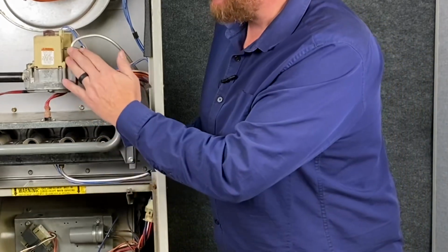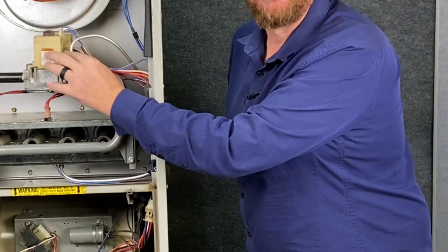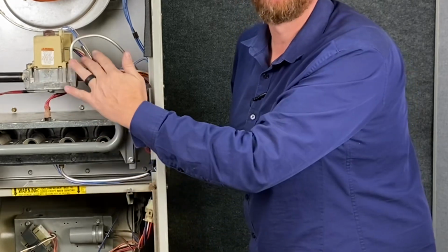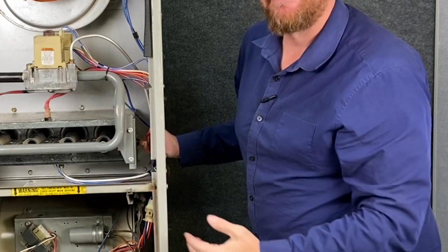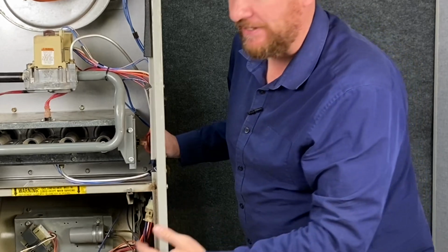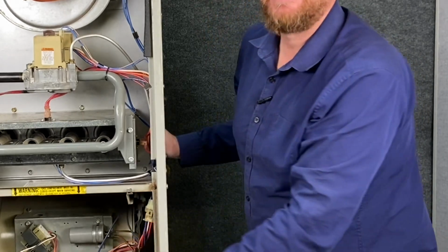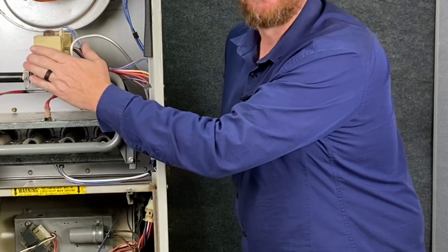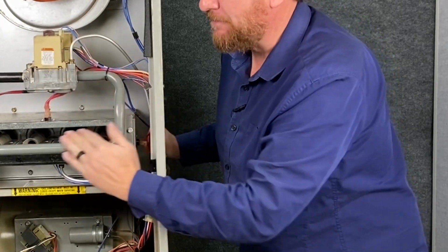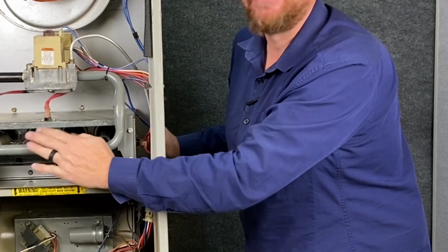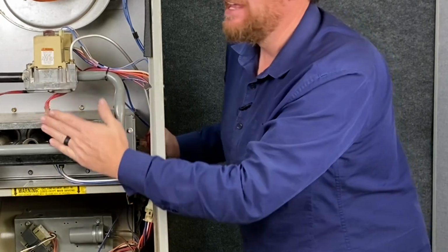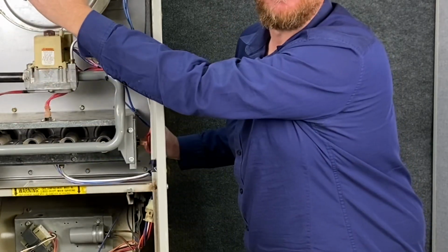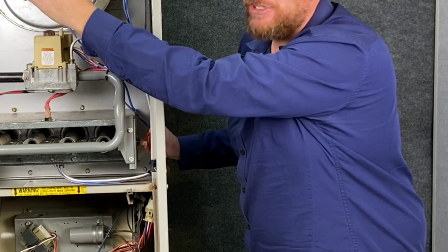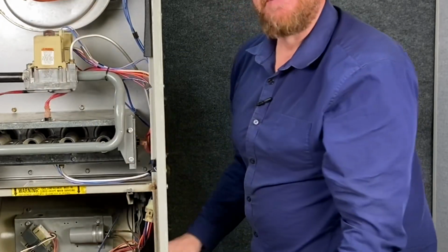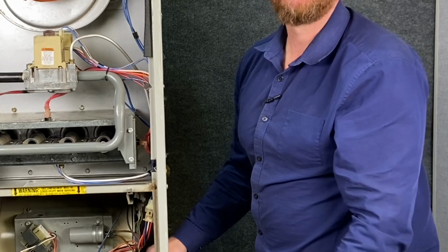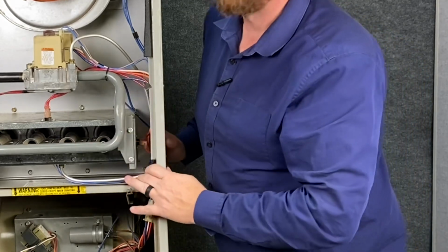So that intermittent pilot is going to be burning all the time while it's running. But when the system cycles off, we're also going to shut off that pilot. So what's going to happen is the house heats up, the thermostat satisfies, it's going to break the R and W. The IFC is going to immediately kill the signal for our combination gas valve. It's going to shut off the main burners and also the pilot. So all the gas is 100% shut off. It's going to continue to run our inducer fan motor to post-purge, clean out that heat exchanger, and it's going to then let the main blower run to cool off the heat exchanger and then cycle it off. That's going to be our sequence of operation.